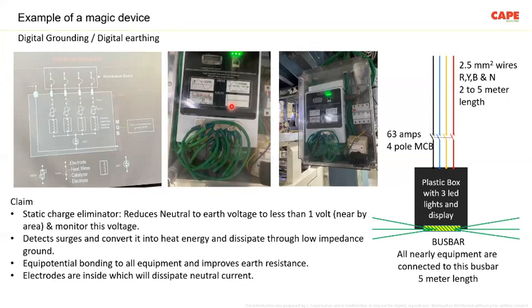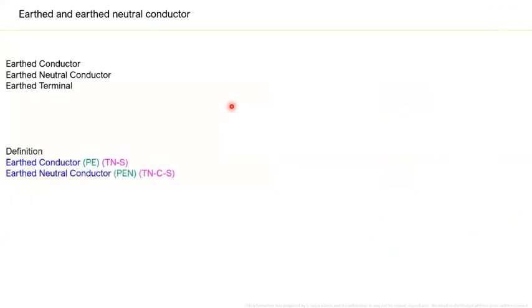And what they do is, inside this device, they simply short neutral and earth together, which is a violation of the rule. The minimum insulation resistance between a current carrying conductor and the earth or the protective conductor inside an electrical installation is 1 megohm. Such devices are violating the rules. Neutral circulating current will flow through the earth conductor, which will create problems of fire, shock hazard, unnecessary arcing, and finally failure of electronics. So such devices, I would recommend, please don't use. It's a violation of electrical safety rule.